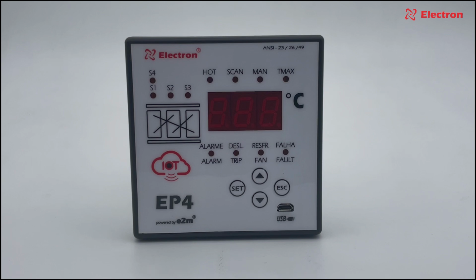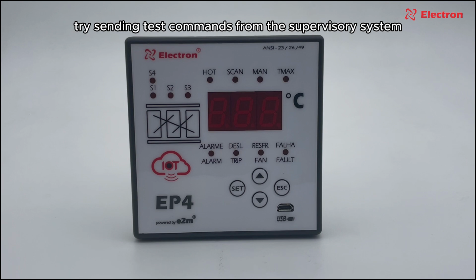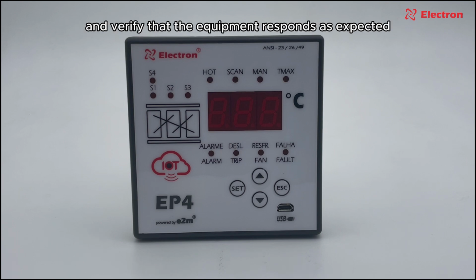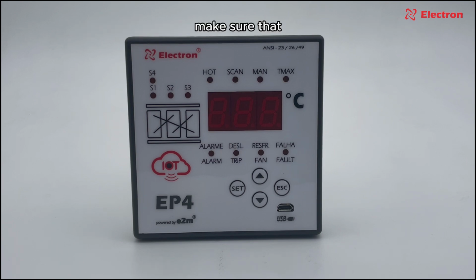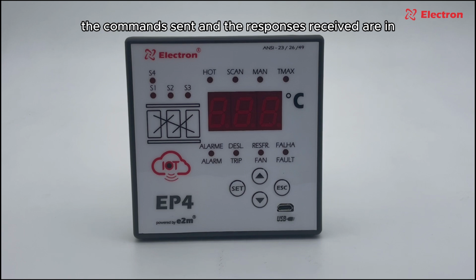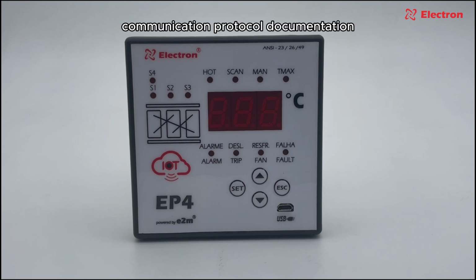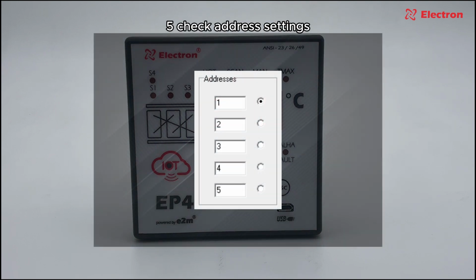4. Use test commands. If you have access to the equipment, try sending test commands from the supervisory system and verify that the equipment responds as expected. Make sure that the commands sent and the responses received are in accordance with the equipment's communication protocol documentation. 5. Check address settings. Check that the address defined in the supervisory system matches the address configured on the equipment.